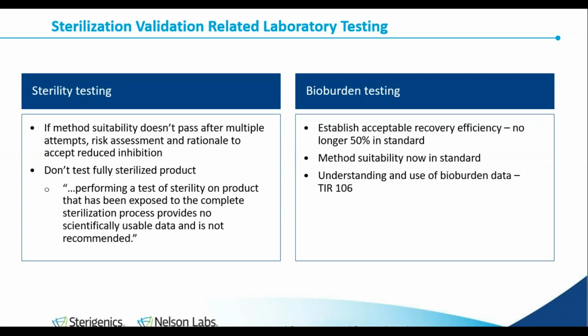Method suitability for bioburden testing is quite important, as it is for sterility. So we now have a method suitability approach that we talk about in the bioburden standard, meaning a screen for any inhibitory substances in the bioburden test.